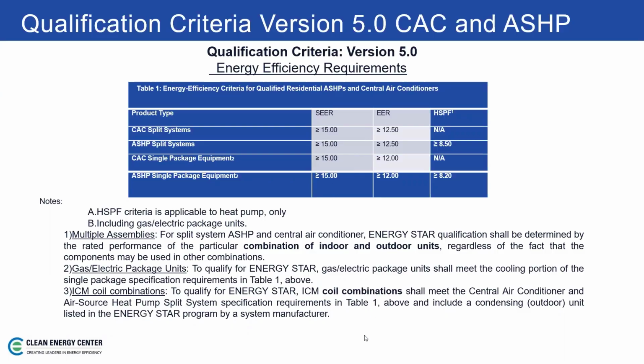There's another note under HSPF. The first note, for split system air source heat pump and central air conditioner, says Energy Star qualification shall be determined by the rated performance of the particular combination of indoor and outdoor units. So if it's an A coil on top of a furnace, that A coil gets matched up with the outdoor unit. And then you would look to see whether or not you can meet this criteria based on that combination, because there are different types of A coils, different types of outdoor units. But I think you should be able to find something that will match up.